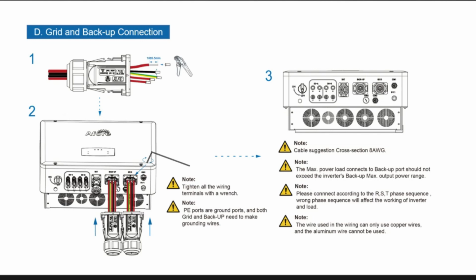Now, something you need to consider is to make sure that your L1, L2, and L3 inside the inverter are the same L1, L2, and L3 that you actually use in the meter. And if you're using it with CT clamps, make sure they go around the same phases as far as that's concerned. Now, that's even more applicable if you're wiring more than one inverter up and you're putting 2 of them.